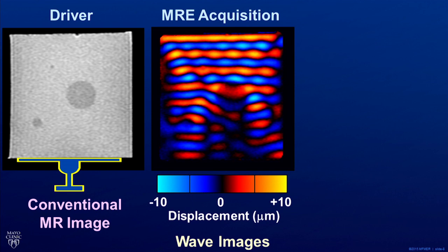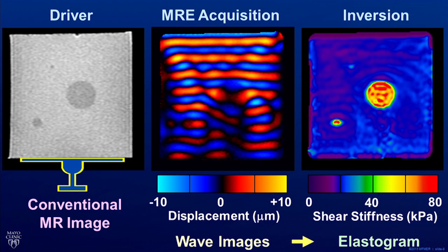This is a gel with stiff inclusions to show how MRI elastography works. It is a three-step process. First, we induce shear waves into the body with a vibration source we call a driver. For the head, it is a soft pillow-like device that results in vibrations similar to an electric toothbrush. In over 250 patients, we have never had a subject complain of discomfort. Second, we perform a phase-contrast MRI sequence that images the waves within the brain. Finally, complex mathematical inversions translate the wave information into maps of stiffness that we call elastograms.